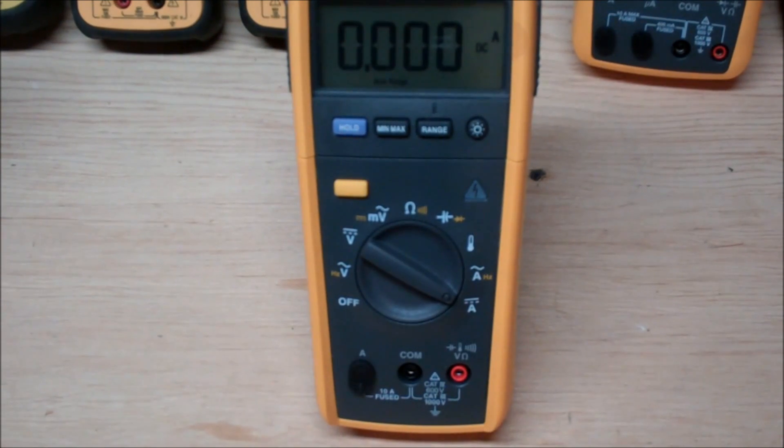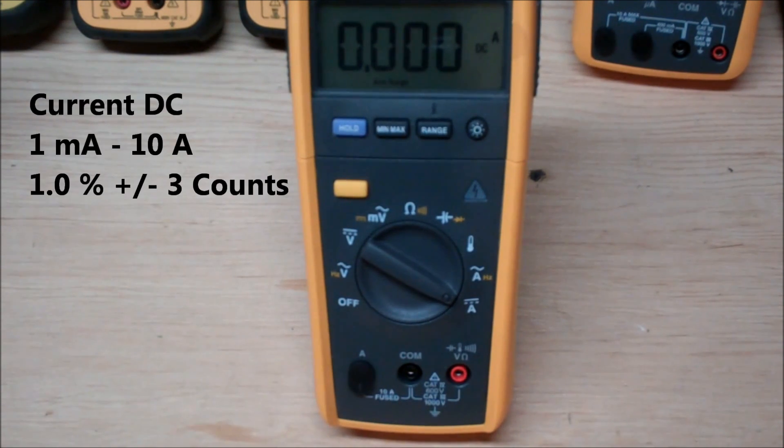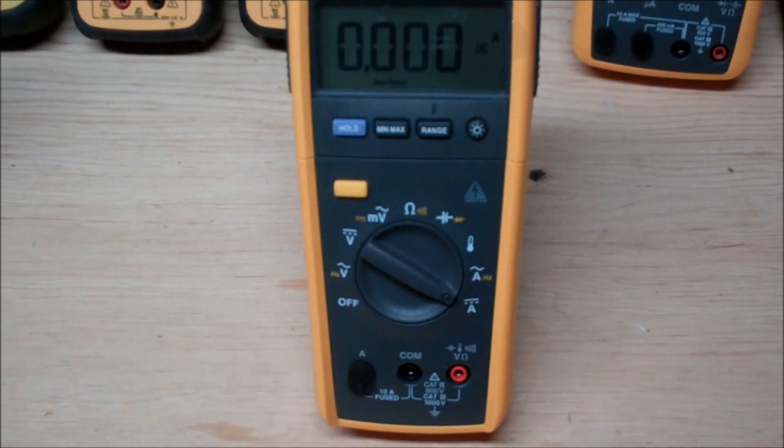Now the final measurement this thing is capable of doing is DC amperage and it's got the exact same range as the AC, from 1 milliamp to 10 amps. And this is going to be really nice because that's going to cover your 4 to 20 milliamp transmitters. So it's got a perfect amount of range for your actual electricians.